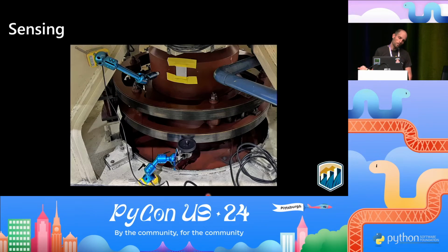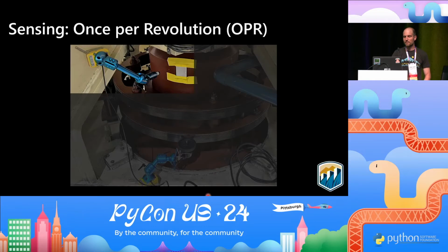So we bring in some sensors. Specifically, this is called a once per revolution sensor. It's really just a laser pulse. When this reflector goes by the little laser dot here, it pulses, and this reflector goes around once per revolution. It's taped to the shaft of the machine. So once per revolution, I see a laser pulse. That'll be important in a sec.